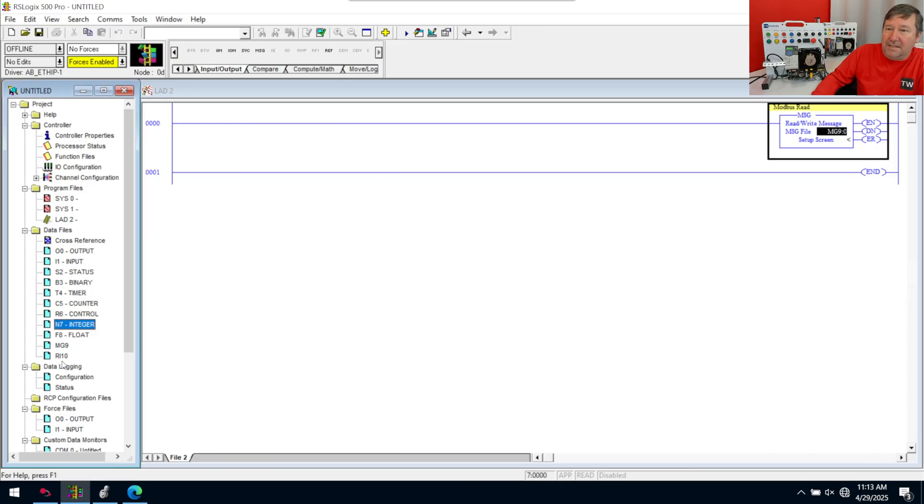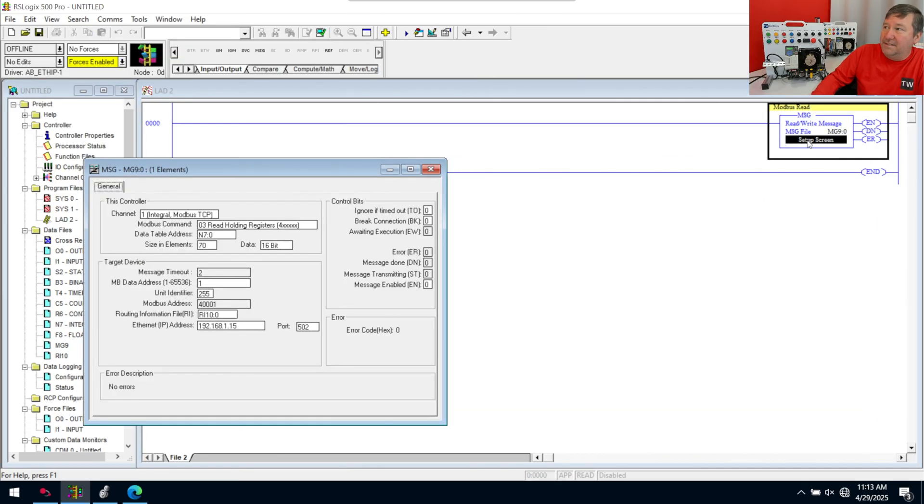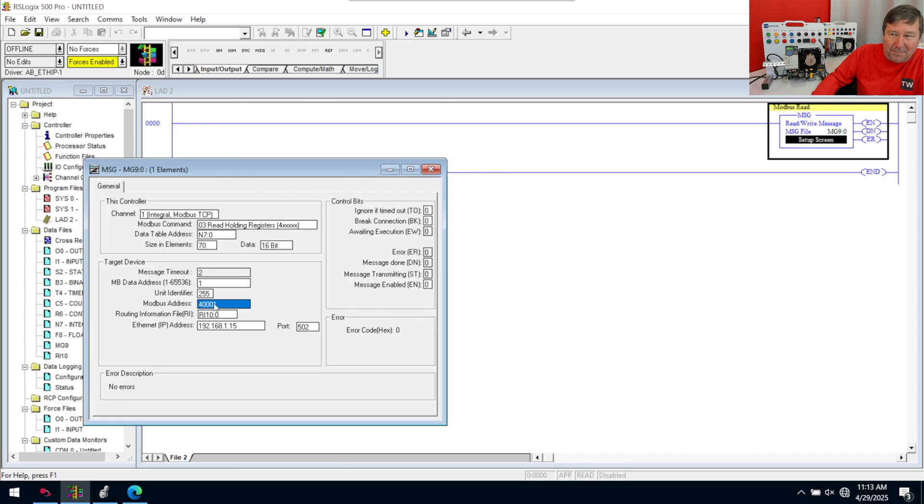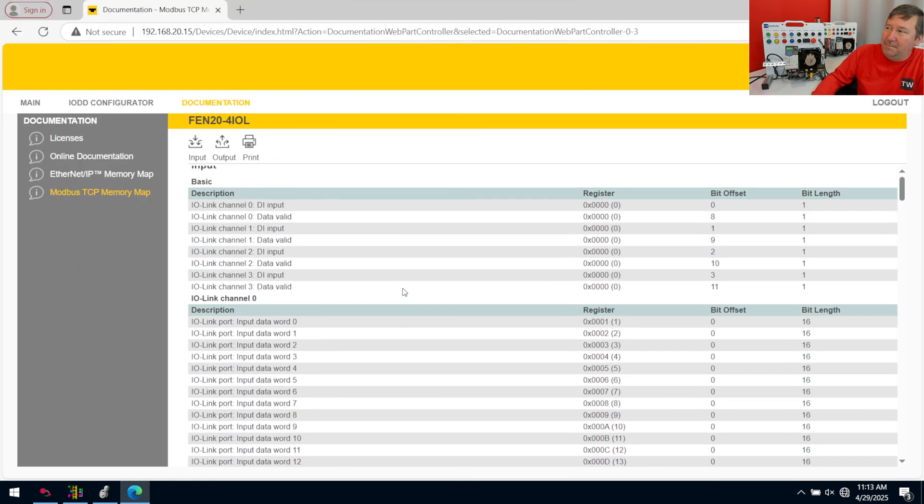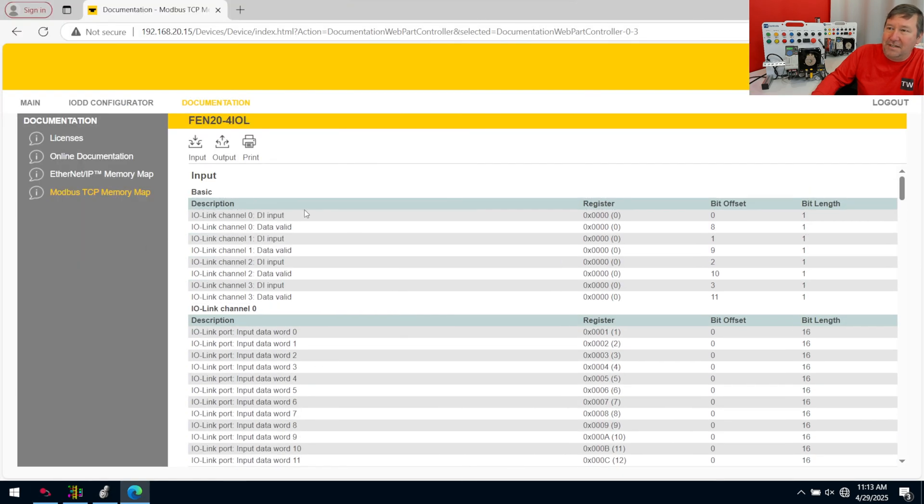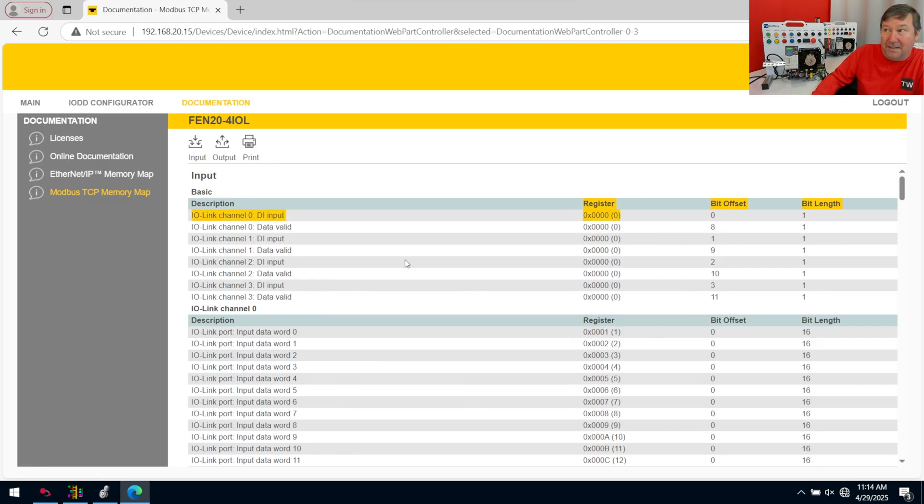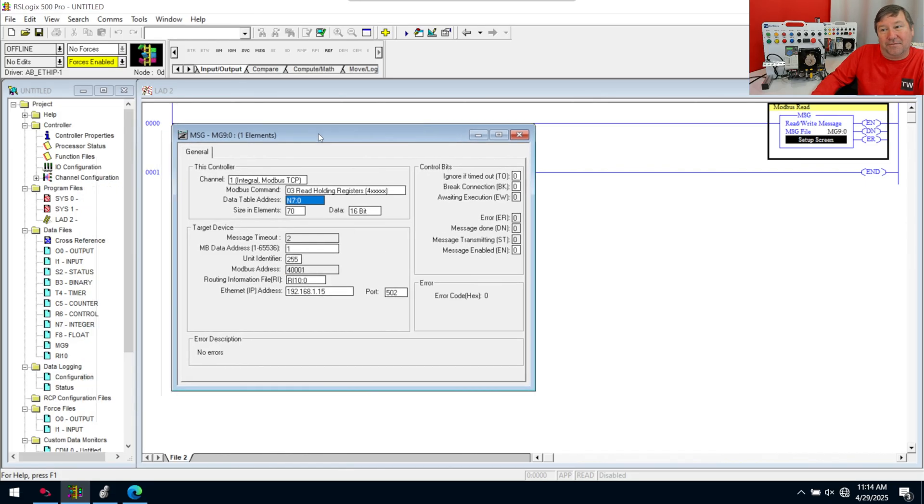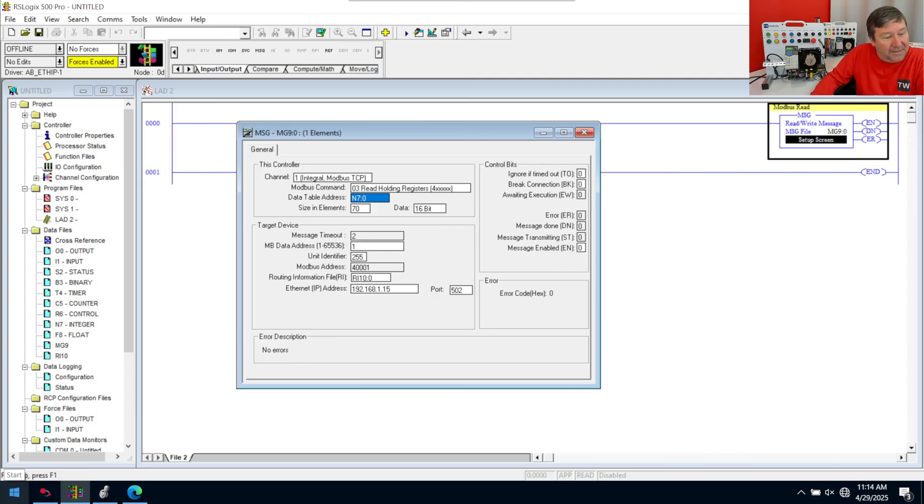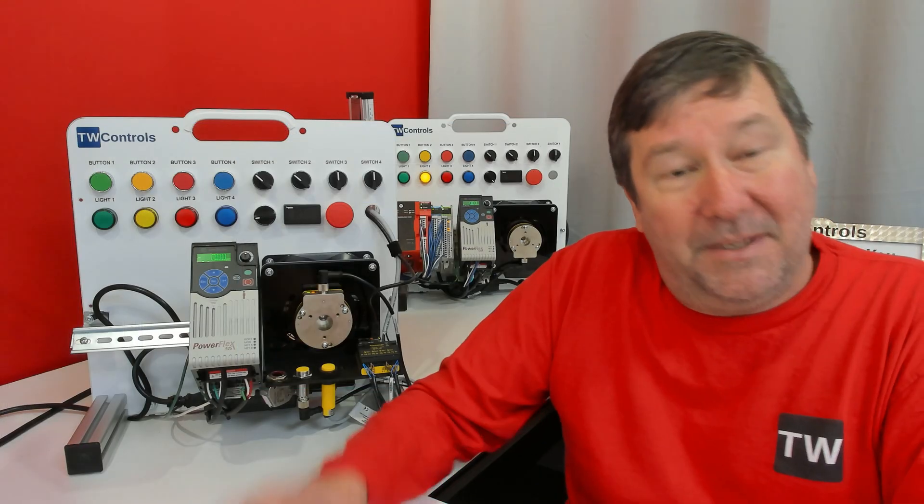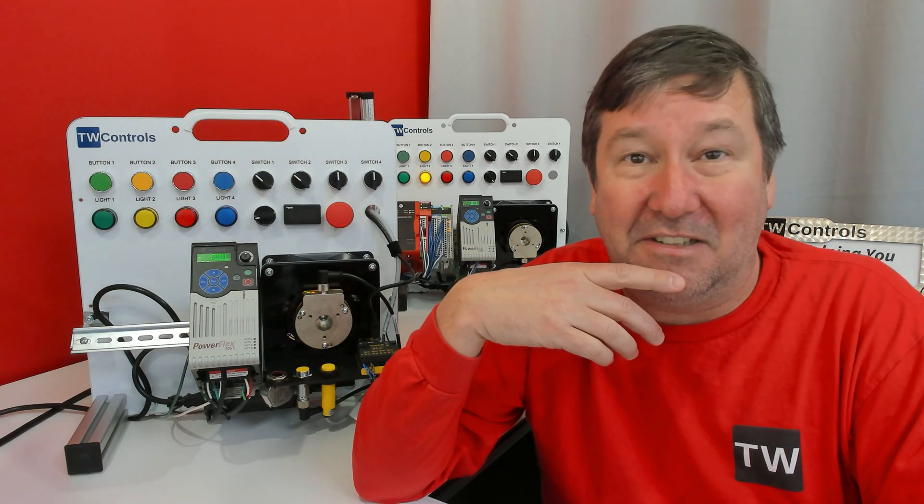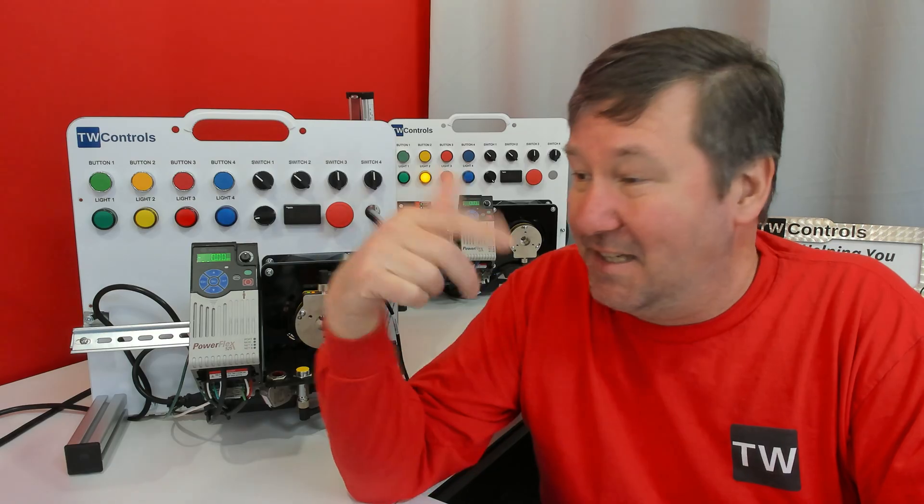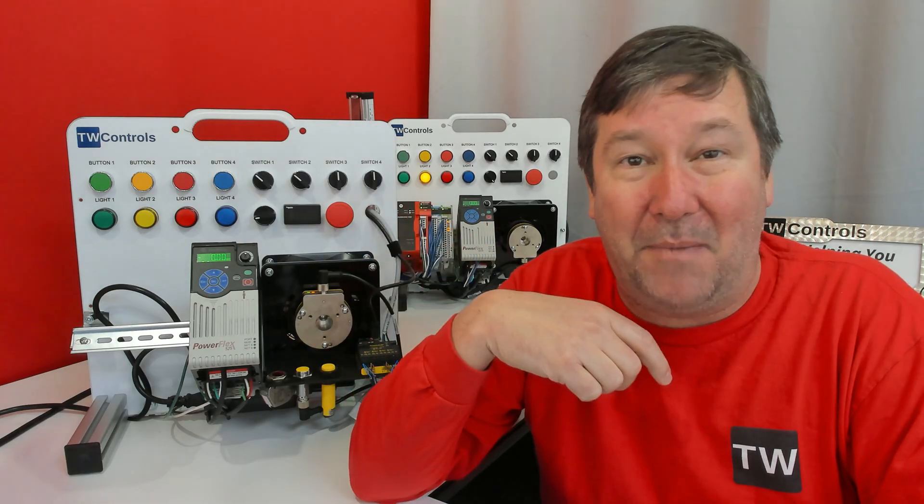Now, we are reading elements one over here. Now, this has been an obstacle before, and I'd be curious if anybody does this. Since we put 40001 here, is it picking up and is it reading register zero or is that register one? I get the feeling it's going to read this one right here. Everything is going to be fine. And coincidentally, since we took element one and put it in seven zero, I believe all our data would line up perfectly fine. So down in the comments, let me know how that works out as far as communicate with Modbus.